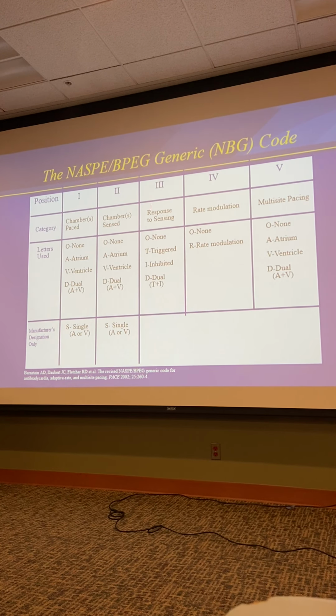There are some manufacturers that have tried to put both of them into the same can. Those details are probably not that important for you guys, except to know that if there is an R in the 4th position, that would be the reason why, if you know that somebody was programmed to a base rate of 60 beats per minute, and they're pacing at 75, and you say, what? They're at 60, why are they pacing at 75? It's probably because rate response is on and they're taking a walk in the hallway or something that has raised the pacemaker's base rate.